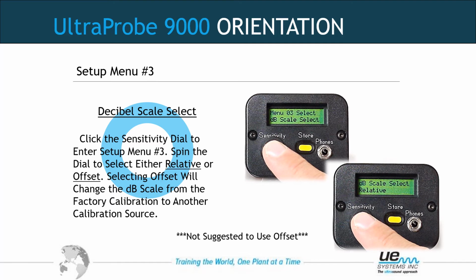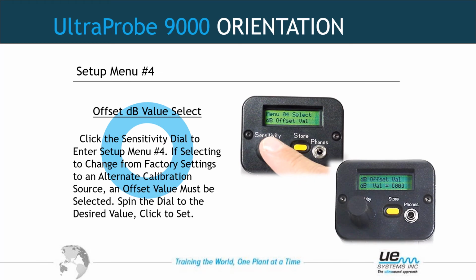So I would choose first to go to dB scale select number 3, select it. The normal position for dB scale is relative to UE Systems calibration. I would change that to offset by spinning the sensitivity dial till it said offset and then pressing the sensitivity button in. That should bring us back to the main menu. Once we're back to the main menu, we'll spin the sensitivity button to the right to menu number 4, select dB offset value. Our value would have been 8 decibels, plus 8 dB. So I would change this to an offset value of 8. The same can be done on the Ultraprobe 401 and the Ultraprobe 10,000. Otherwise, we leave the scale in relative and the dB offset value would be 0 in normal circumstances.